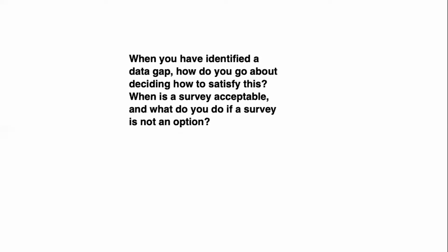But as long as you demonstrate that you have a plan and intend to launch that, from our experience, notified bodies are right now okay with that. In other words, how do you go about deciding to satisfy this? Well, you tell the notified bodies that you've identified a gap and how you're going to mitigate that gap going forward. And yes, a survey is one way of doing that.